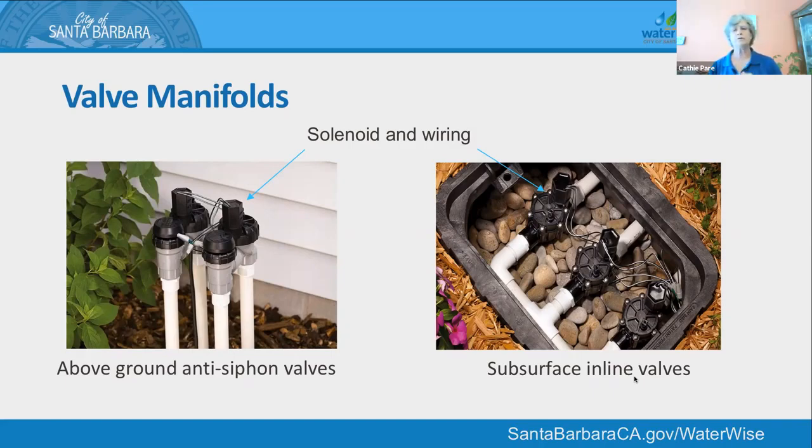It's a good place to look if you're having problems with controllers not working. Make sure that the wire nuts that are holding the wires are actually dry and they're in a silicone nut, because those inline ones, it's like being in a bathtub. So water and electricity, they don't play well together. Next slide.